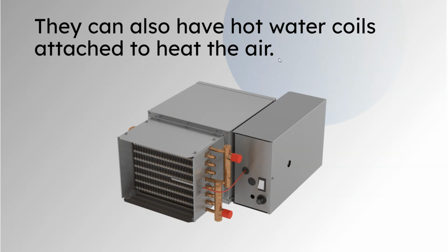The next one is a VAV with a hot water coil attached to it. So you can have reheat on the VAVs. Most typical VAVs are supplied with 55-degree air year-round, Fahrenheit. I'm in the US, so I go by Fahrenheit. That's about 13 degrees Celsius for anyone not in the US. So in most cases, the air handler is always going to supply 55-degree air to the VAV. Now the VAV can shut itself down a little bit and provide less air to the room, but if that's still not enough and it's still overcooling the room, then you need a reheat. This would be a hot water reheat. You would have a valve with an actuator on it, and the controller would open the valve as needed to reheat the air to warm the space.